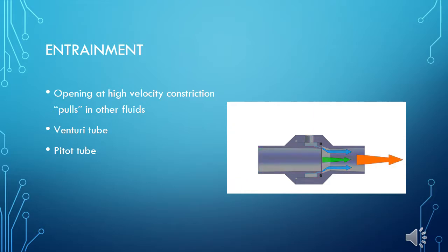So you can determine that a predetermined amount of air can entrain consistently, but you end up having a problem because you can develop a little bit of back pressure downstream from that entrainment port, and that can cause the amount of fluid or air or gas that is entrained to decrease. Of course they already discovered this, so they came up with the Pitot tube, which is a way to overcome the problem by restoring fluid velocity and lessening the downstream pressure. I always think of it as kind of a pressure relief, so you don't get a buildup of back pressure.